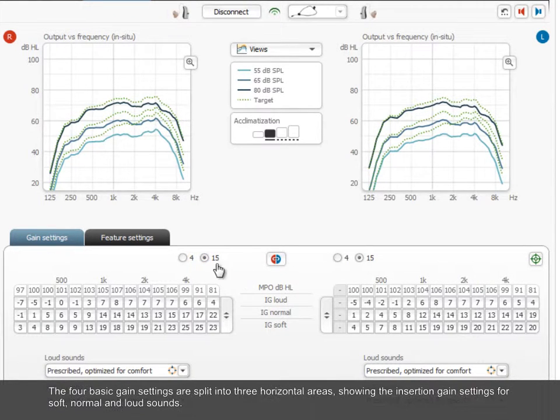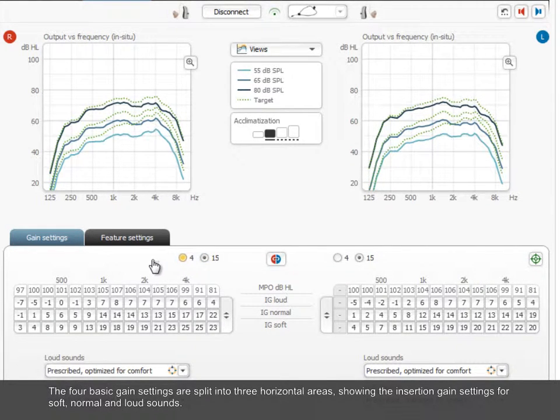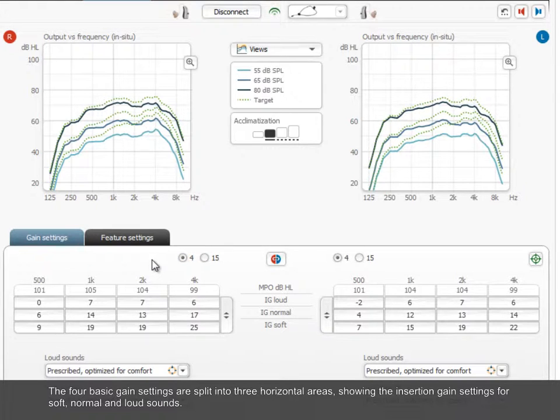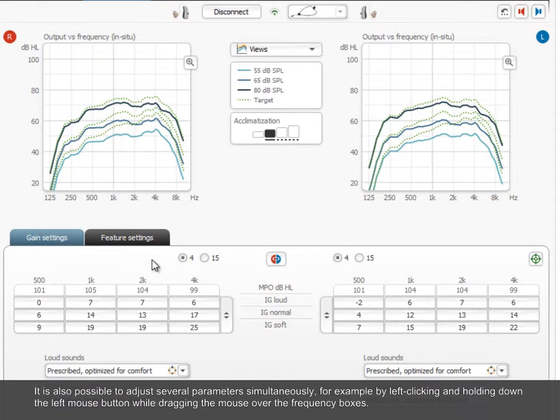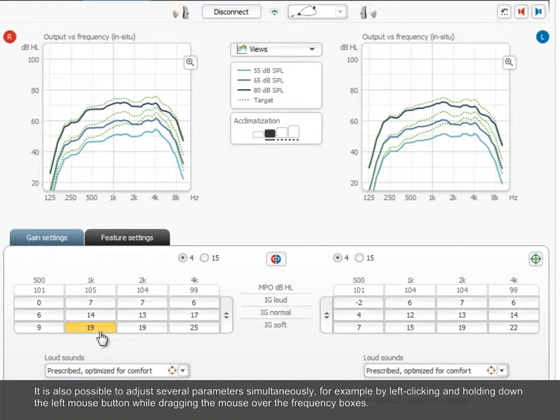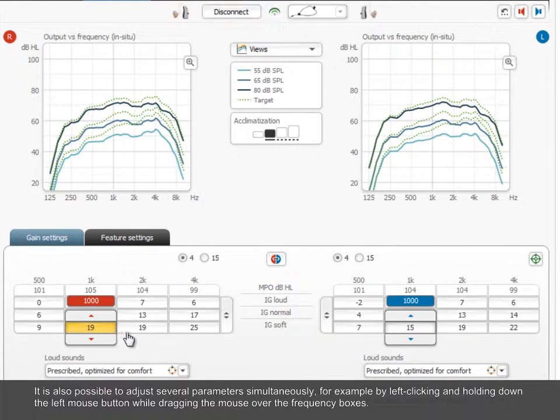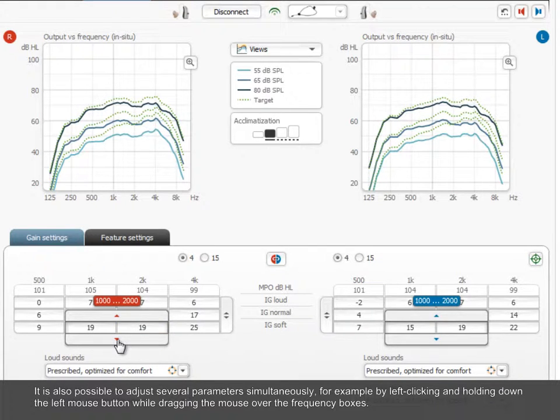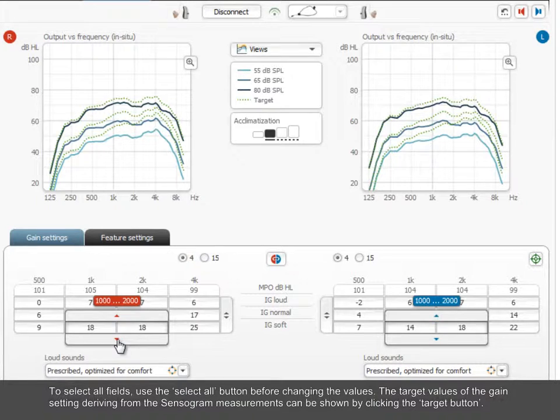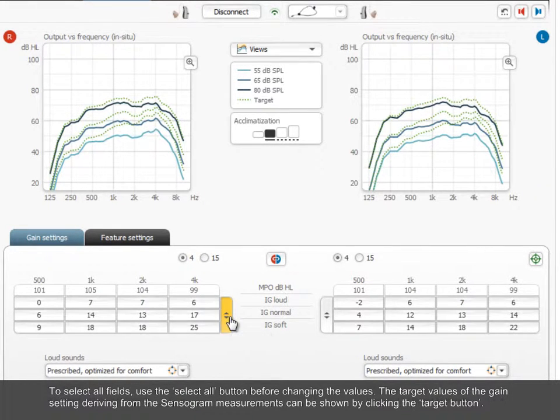The four basic gain settings are split into three horizontal areas, showing the insertion gain settings for soft, normal and loud sounds. It is also possible to adjust several parameters simultaneously. For example, by left-clicking and holding down the left mouse button while dragging the mouse over the frequency boxes. To select all fields, use the Select All button before changing the values.